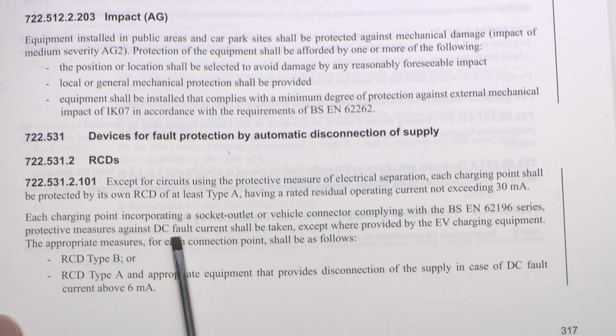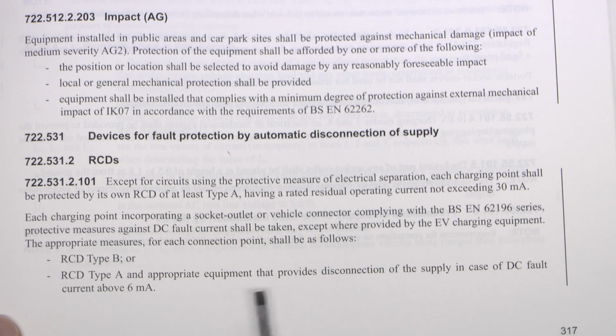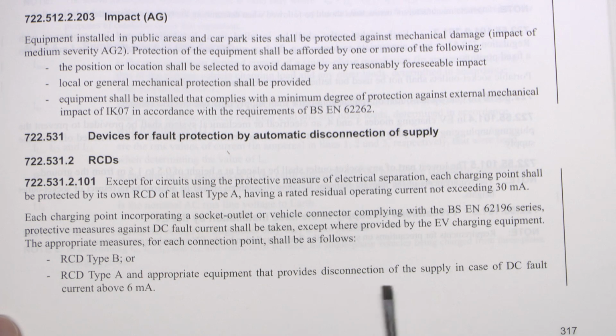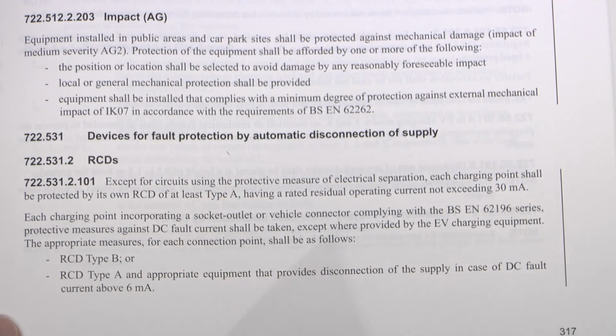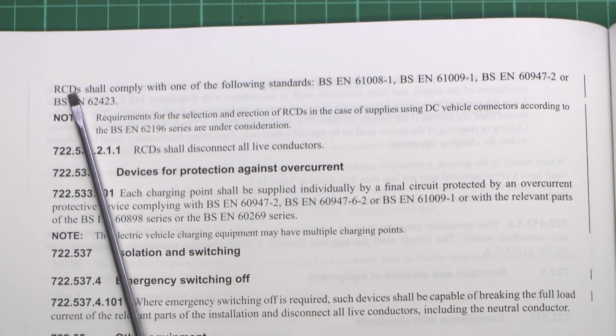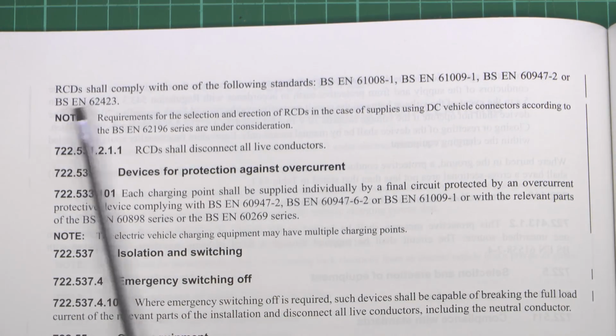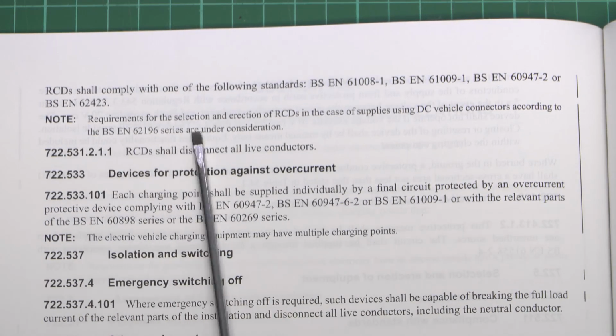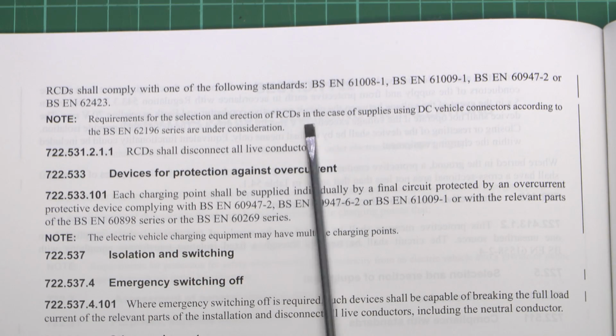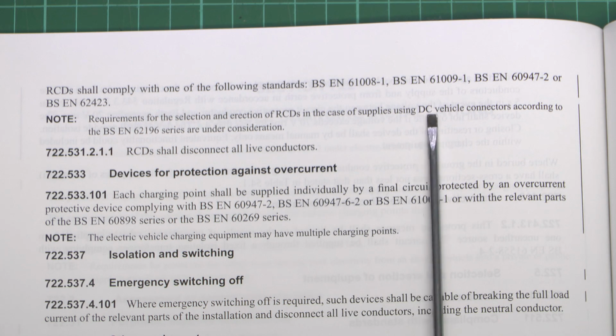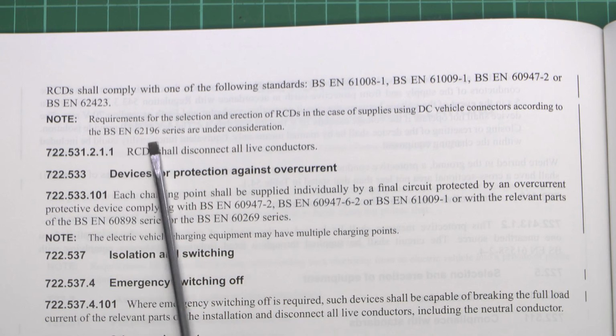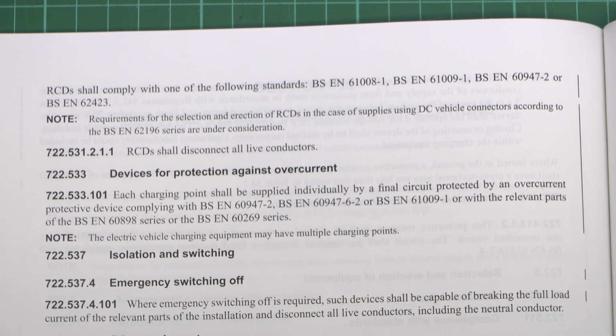Protective measures against DC fault current should be taken, except where provided by the EV charging equipment, and the appropriate measures are an RCD type B, an RCD type A, and appropriate equipment that provides disconnection of supply in case of a DC fault current above 6 milliamps. And continuing over the page, RCDs shall comply with one of these standards here. And again, we've got a note now about the requirements for the selection and erection of RCDs in the case of supplies using DC vehicle connectors. And again, that is actually under consideration.